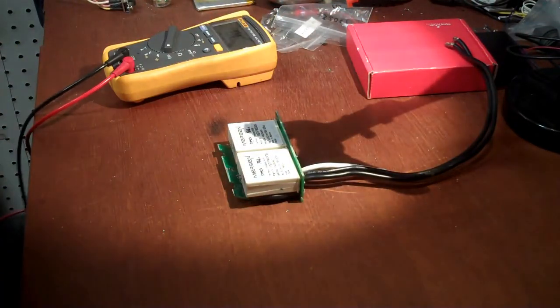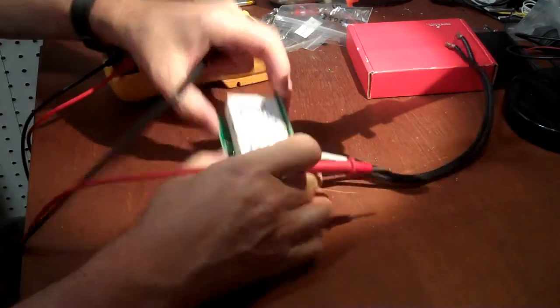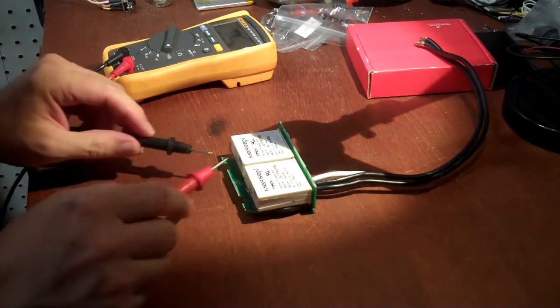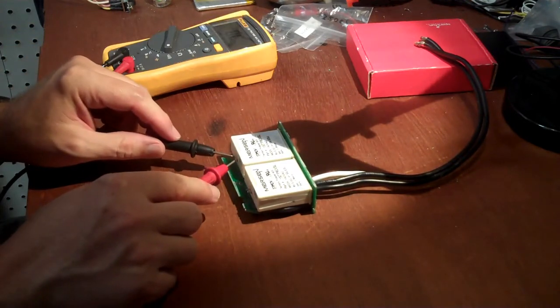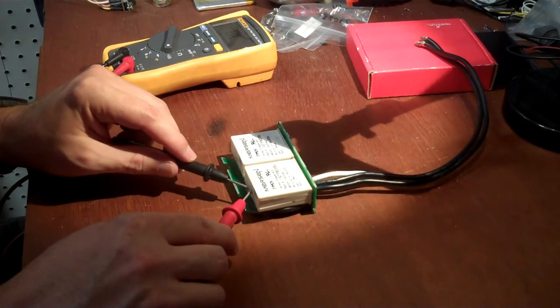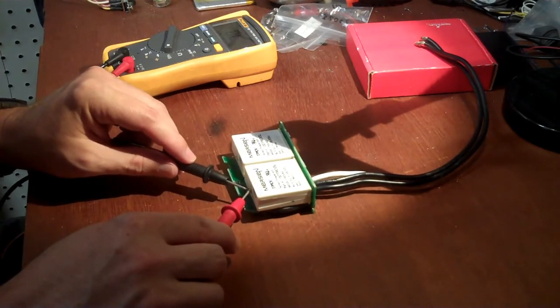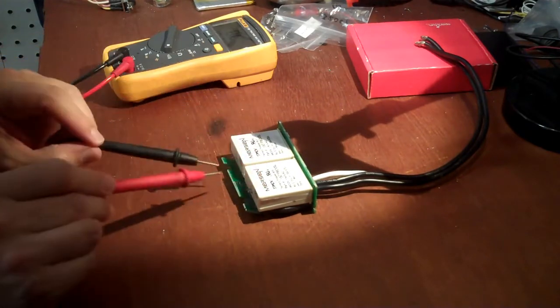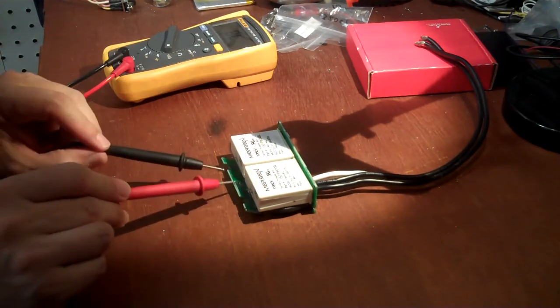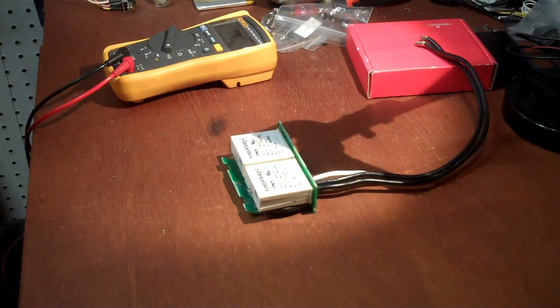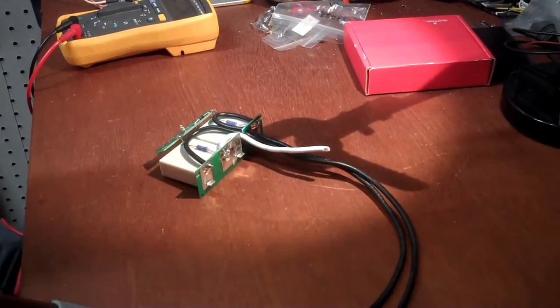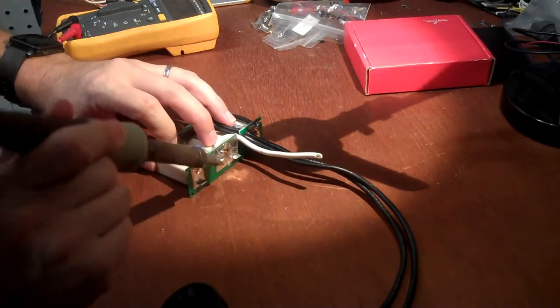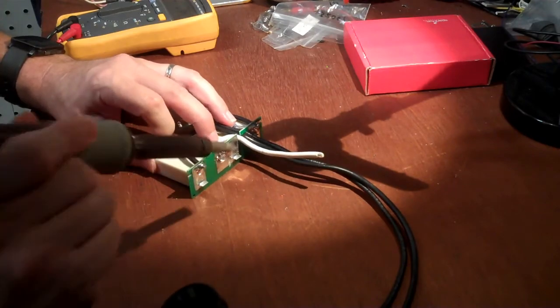Double check the spec sheet on these guys. And these are the ones that do not have a visual indicator here. But the spec sheet says these are normally open micro switches. And both of these micro switches are open right now. So it's possible these two guys are still good and the problem is with the indicator light or the indicator circuit.